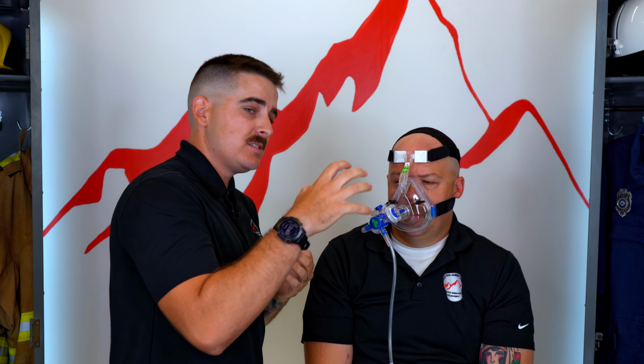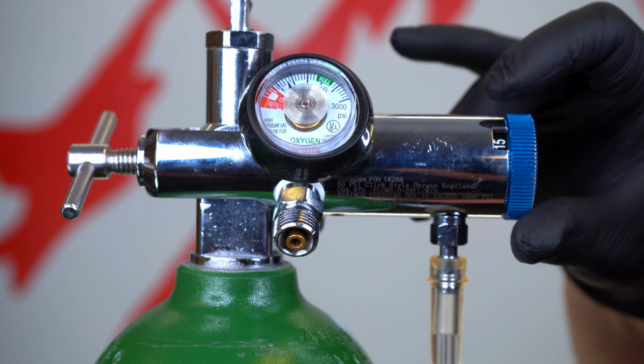Now, every time Chris takes a deep breath, I look at the manometer at that peak inspiratory pressure, which is going to be the maximum amount of resistance going into our patient's airways. And so Chris is breathing in, and I'm getting a reading of 5 centimeters of water pressure as his CPAP, so that continuous positive airway pressure. And so at this point, we adjust our flow up to achieve 10 centimeters of water pressure, still in that CPAP mode. Okay, nice deep breath, Chris. Good, and now I'm seeing that manometer is at 10 centimeters of water pressure.